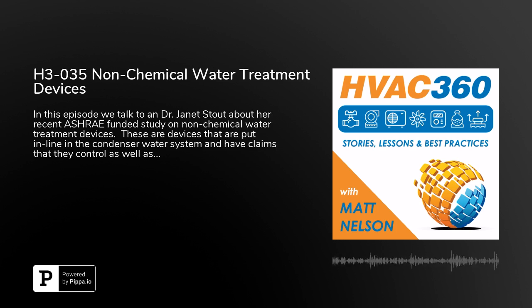I guess in going through these devices, if you're to read the study, what kind of things are important to focus on? Well, because this is essentially an assessment of the control of bacteria, the study design is pretty straightforward. For each device, we just had to verify that the cooling towers were both the test cooling tower and the control. So side by side, we've got one of the model cooling towers with the test device on it and an exact replica sitting next to it that doesn't have the device on it. And we're sampling twice a week the bulk water, once a week the biofilm coupons for the total bacteria and Legionella. And we're comparing to see whether there's any difference between the control without a device and the device.